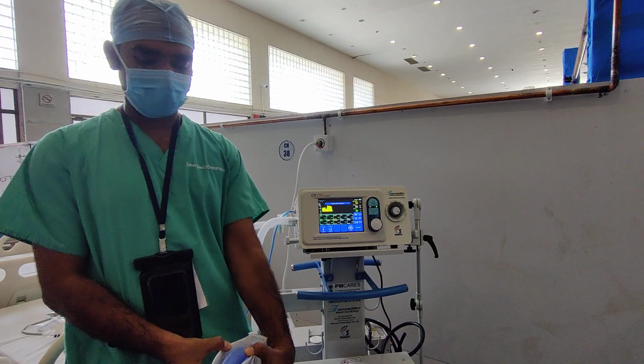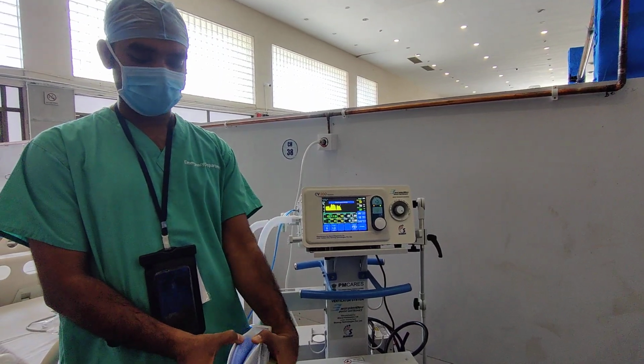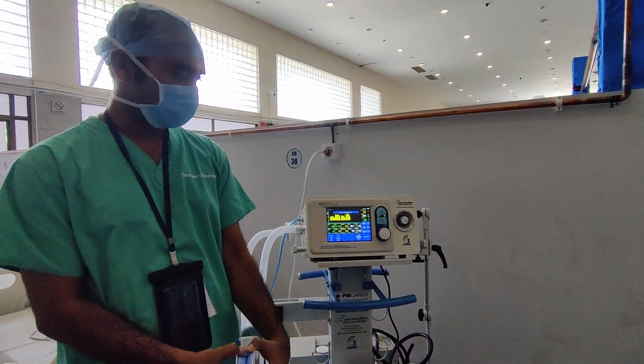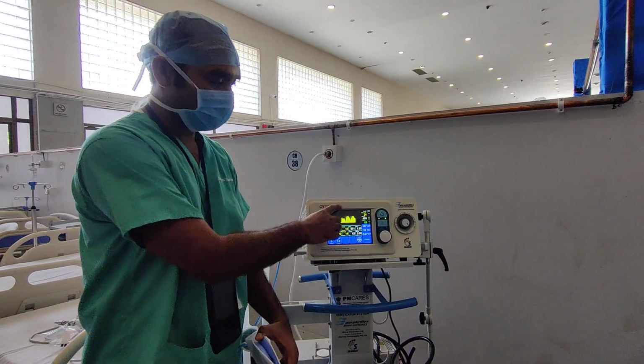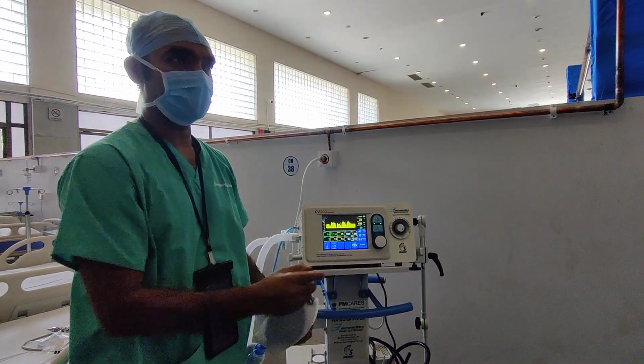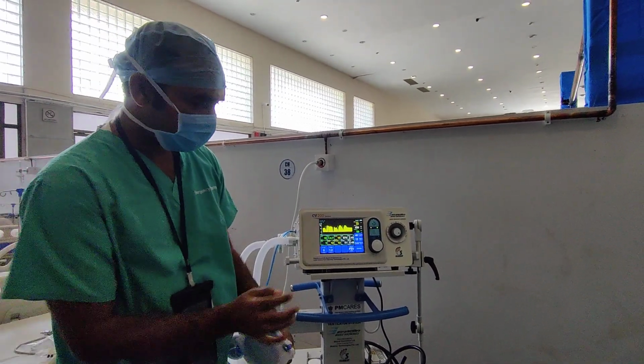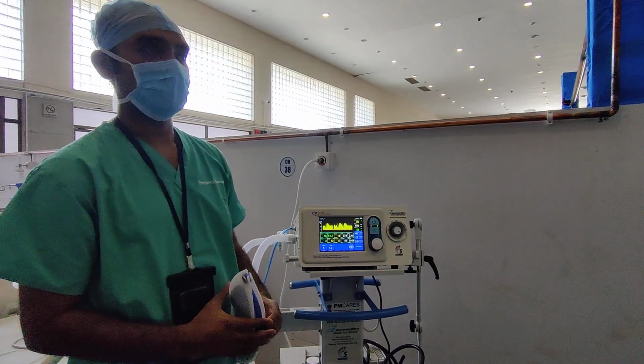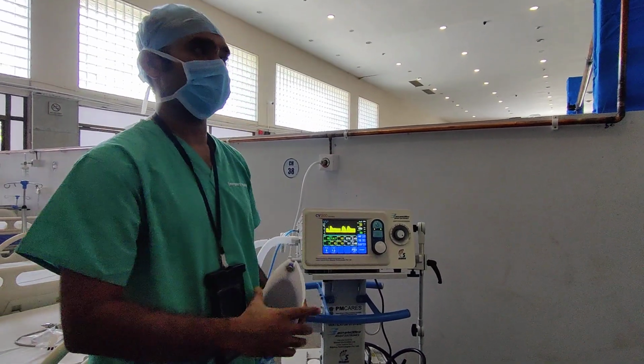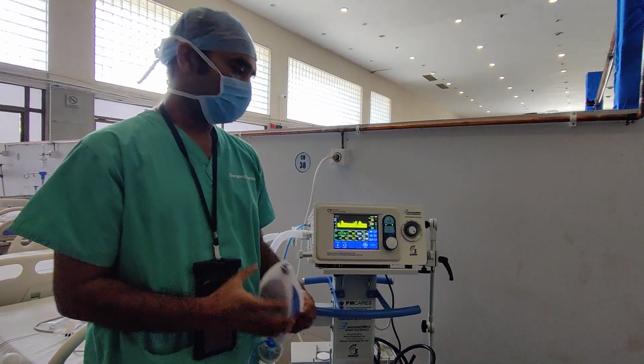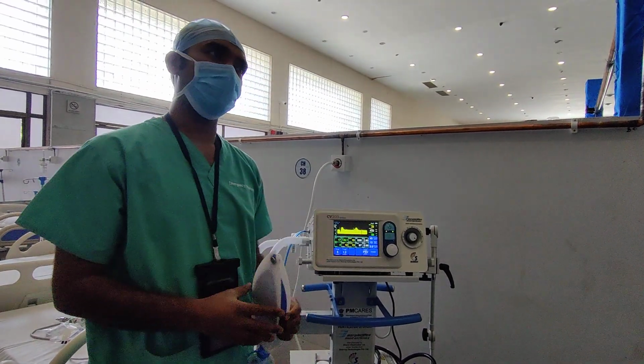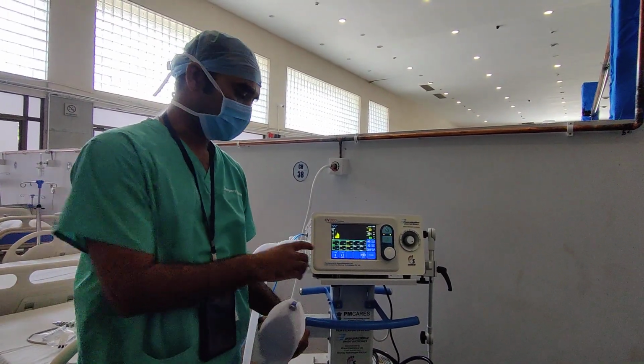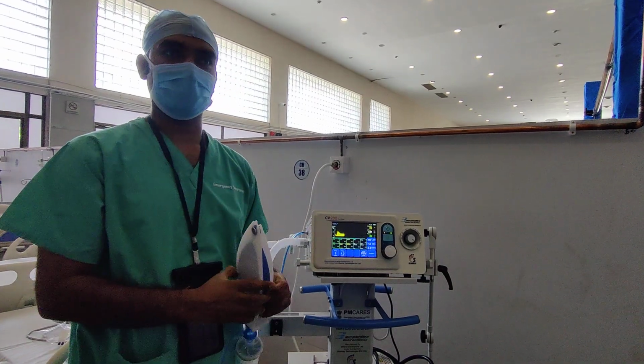This is your patient effort, and with the patient effort, the machine will give a volume. You can see the waveform is coming, some values are coming here. What you're interested in here is volume. See, VTE means expiratory tidal volume. What you want to aim for here is 400 to 500. You can adjust your pressure support as per your target.